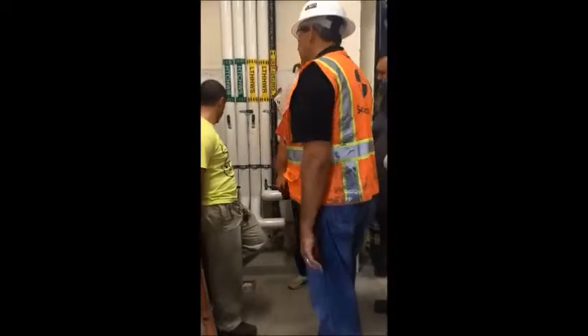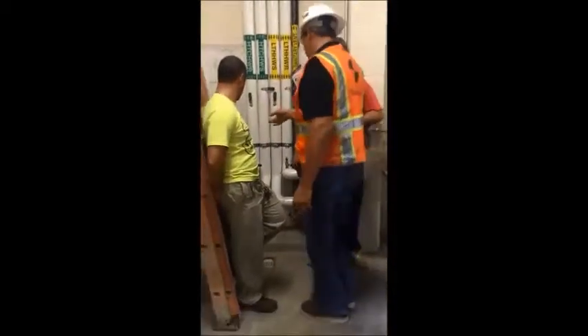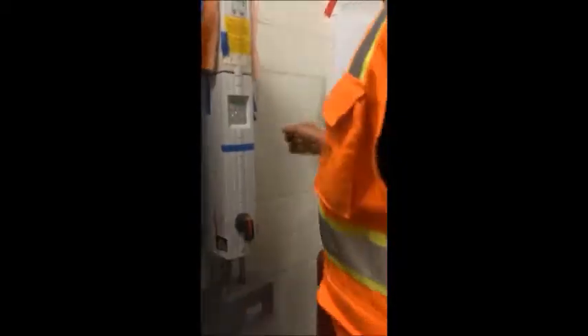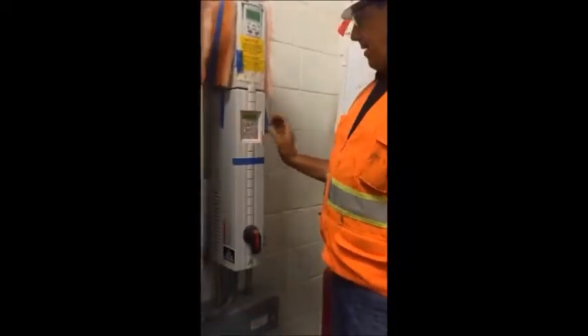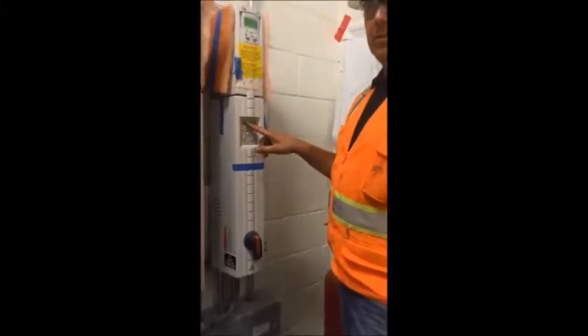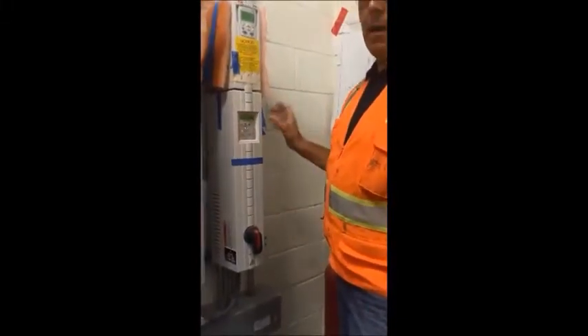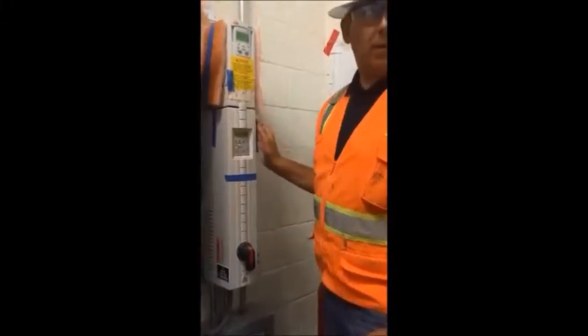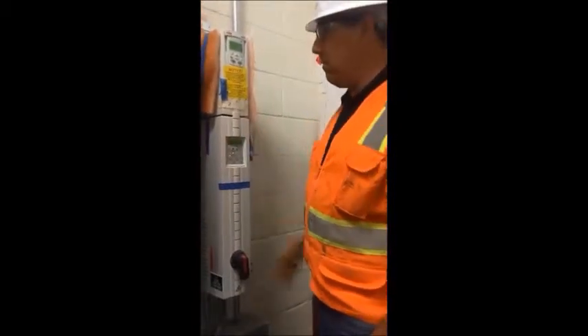Obviously, I'll remove all the filter media, but the bypass section is on most of these units, you bypass it off. Again, that way if it's put in automatic, I select it as off, so somebody just can't turn it on. You have to go to the bypass mode and put it on and then enable it and start it. Okay? No problem.